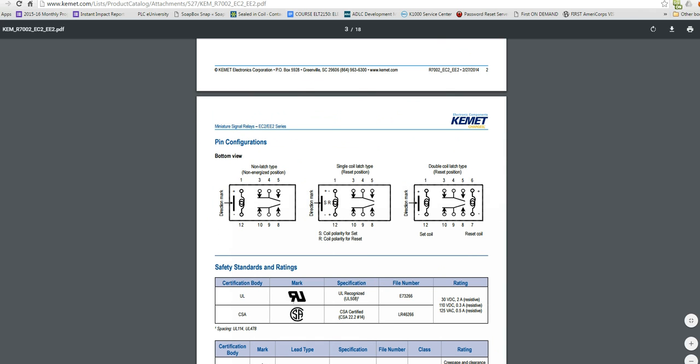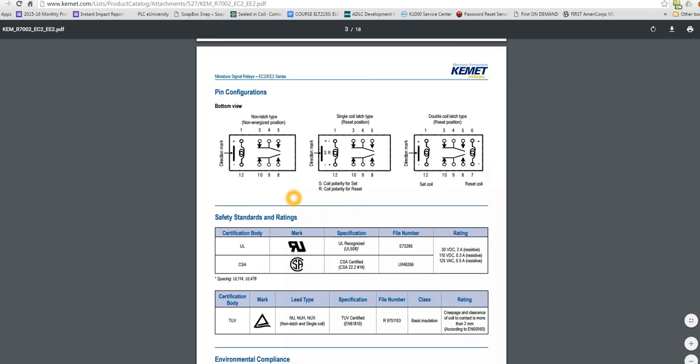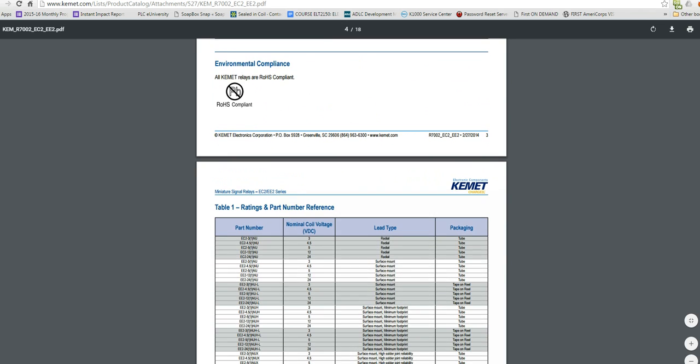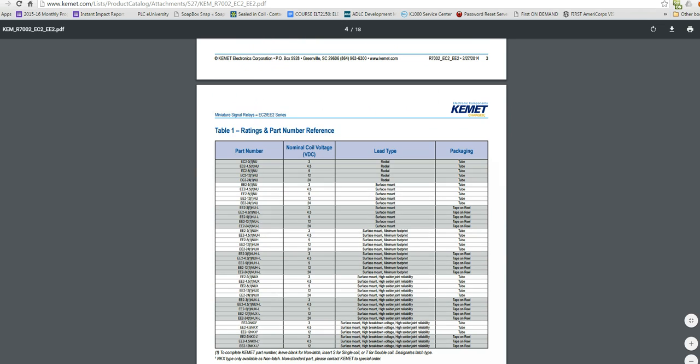You can see the coils are connected to pins 1 and 12 on all three of these, 1 and 12. And the contacts, the center contact is on pin 4 and 9. The normally closed contact is on 3 and 10. And the normally open contact is on 5 and 8. And they've got a couple other options here. This datasheet covers a large number of relays you can see that they produce.